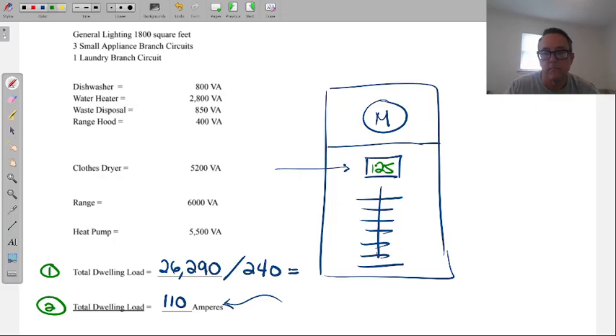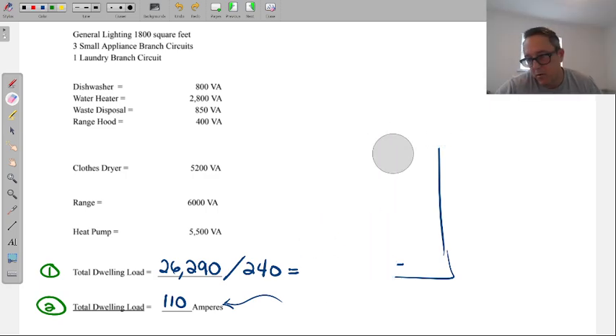I ran into this doing two houses. On one, I did the load calculation like we just did and landed at 150. I went looking for the meter combo and found only 125 and 200 — nothing in between. It was impossible for me and the homeowner to find one online, on Amazon, eBay, anywhere. So in the end, we resubmitted the plans to the city for a new permit, which didn't take more than a couple of days. We can only increase, not decrease — I can't go to 125 when I need 150 — so I made the main breaker 200 and increased the wire size a bit. The homeowner paid for everything, and it was fine.